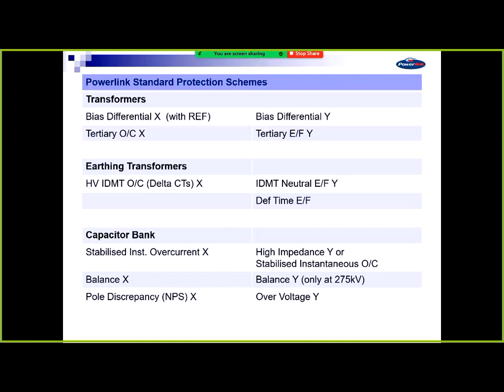They're standard, and what we've found for our network is that it's cheaper for us to have the one type of protection for different voltage levels. Having different protections for different voltage levels means carrying more spares, and a newer design, you've got to think about it. It just keeps it simpler for everybody. We've got one panel and it's the type of protection, feeder, transformer, and it doesn't matter what voltage level it's at.